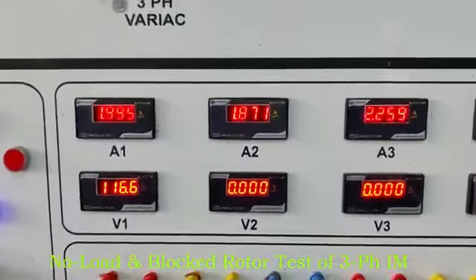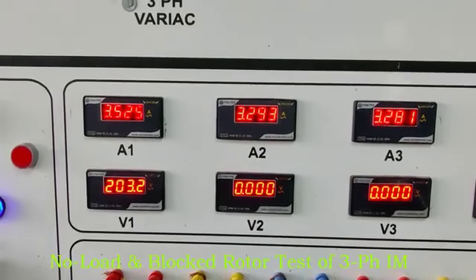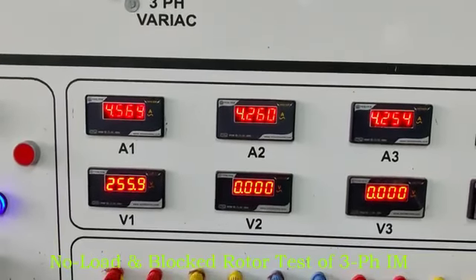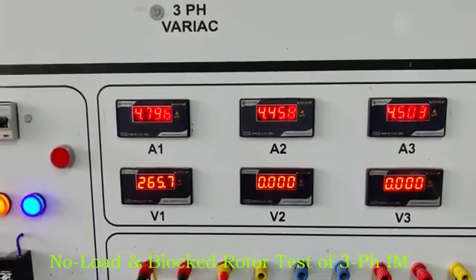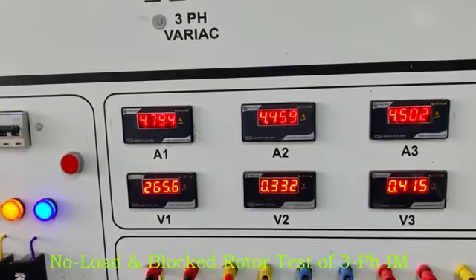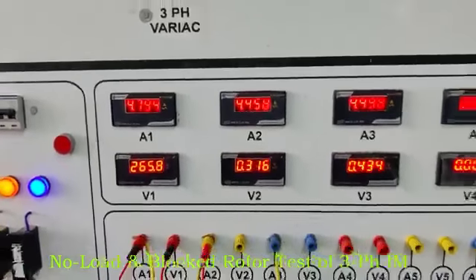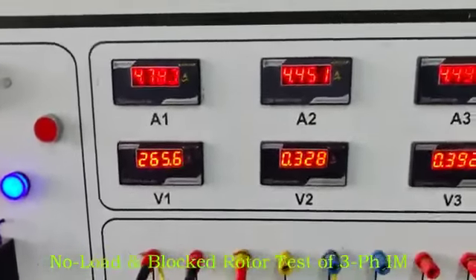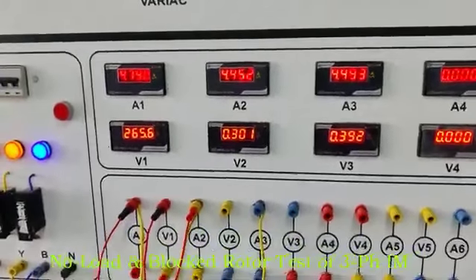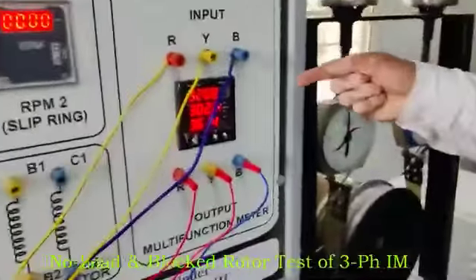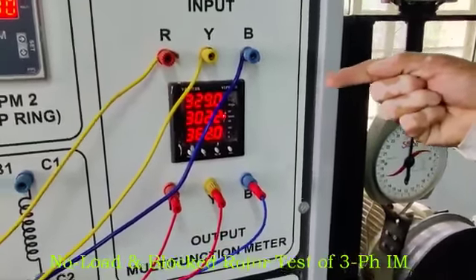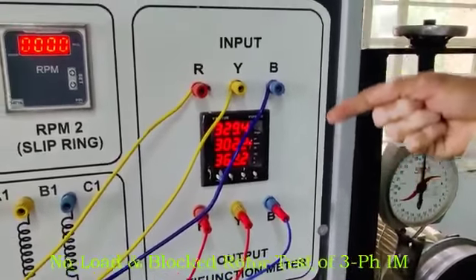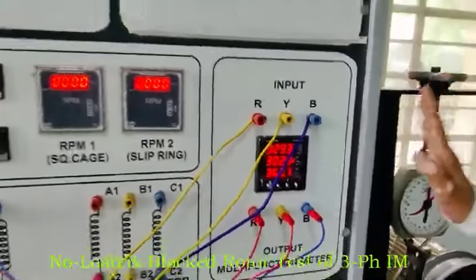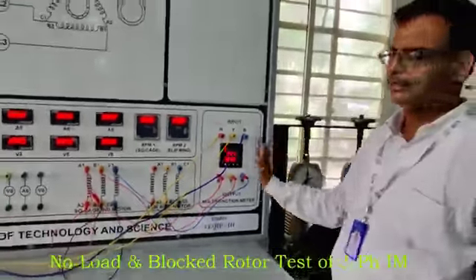Readings: 1.4, 1.9, 3.5. Yes, this is the rated current. 4.7, it's the rated current. 4.4, and the short circuit voltage V1 only here, and it's a power. The power is high as compared to no load: 328, 302, 362. By adding all this power, we can calculate the short circuit or blocked rotor test power. So these are the readings for the blocked rotor test.